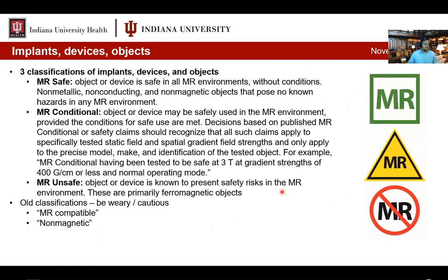There are 3 classifications: MR safe, MR conditional, and MR unsafe. MR safe objects or devices can go in without conditions. They are non-metallic, non-conducting, and non-magnetic objects that pose no known hazards. The conditional objects are objects or devices that can be safely used in the MR environment, providing certain conditions are followed. Finally, unsafe objects are objects or devices that are known to present safety risks in the MR environment. These are primarily ferromagnetic objects, although they don't necessarily have to be ferromagnetic.